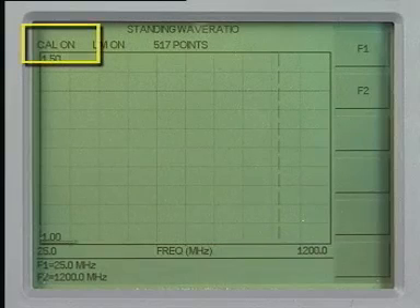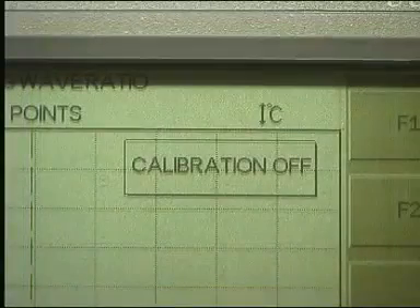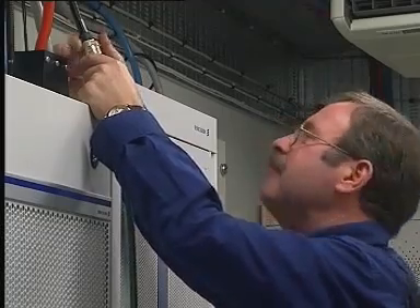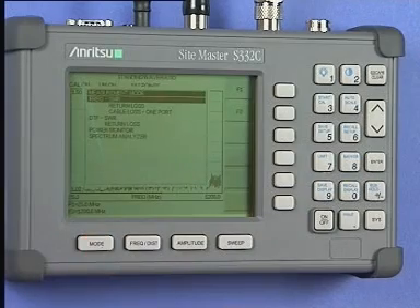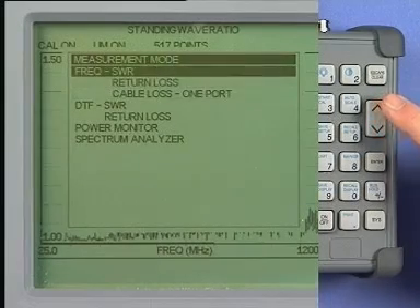Now you will see the message Cal On at the top left of the screen. If the instrument was not calibrated, then you would have seen the message Cal Off, as well as a very large calibration off warning box in the middle of the display. Did the calibration go OK? Connect the Site Master phase-stable extension cable to the selected jumper or feeder cable. To begin the measurement, press the Mode key. The Up-Down key will now scroll the display up and down the screen menu. Select Frequency SWR and press the Enter key.